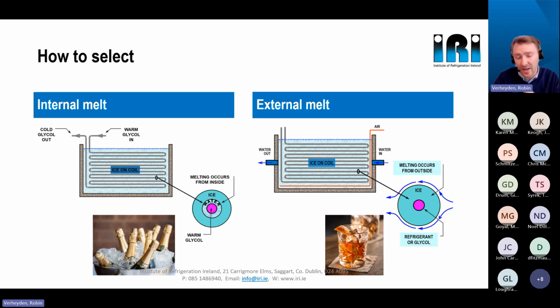That second circuit is actually water in direct contact with the ice. As you can see on the schematic, the water flows over the ice cylinder and into the tank. So it's not a closed system like internal melt, but really an open system, with direct contact of water with the ice block in a second circuit.